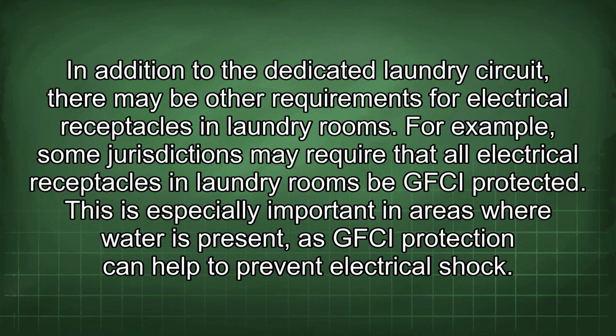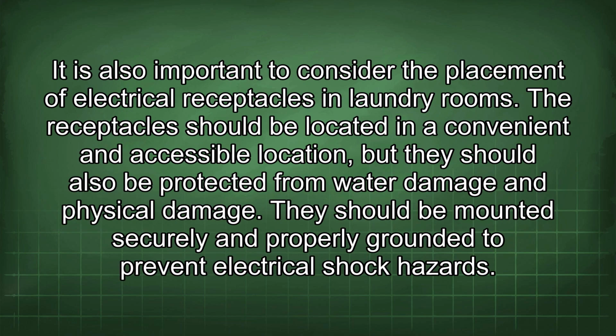For example, some jurisdictions may require that all electrical receptacles in laundry rooms be GFCI protected. This is especially important in areas where water is present, as GFCI protection can help to prevent electrical shock. It is also important to consider the placement of electrical receptacles in laundry rooms. The receptacle should be located in a convenient and accessible location, but they should also be protected from water damage and physical damage. They should be mounted securely and properly grounded to prevent electrical shock hazards.